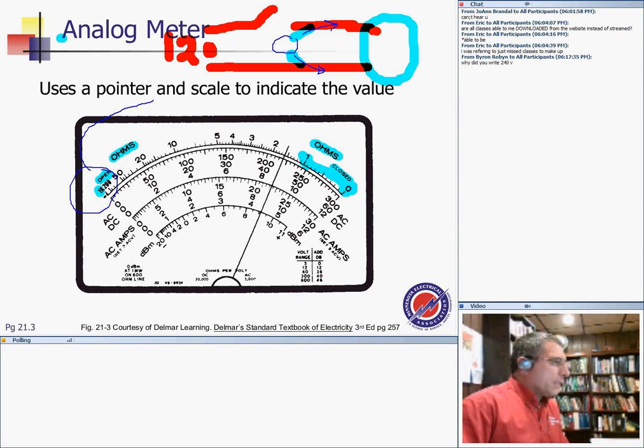The other thing I want to mention, look at this one. I have AC, DC, different levels from 0, 50, so you can set yourself to be more sensitive. You can boost your scale all the way up to 12 to get a more sensitive measurement, then go up to 60 and all the way up to 300 by adjusting your scale. There's voltage, and right underneath it is your current, with the same scale, more sensitive to less sensitive.